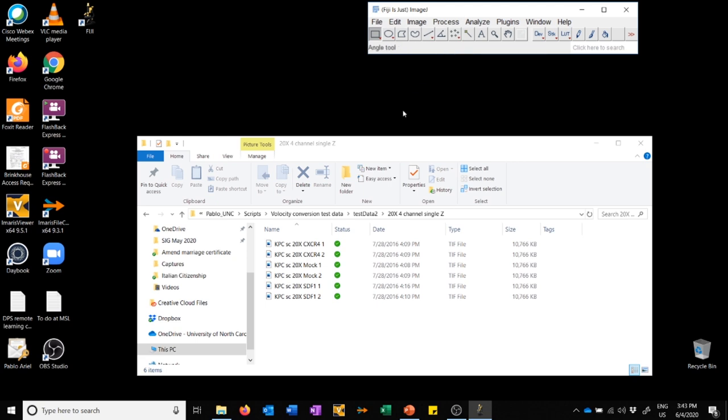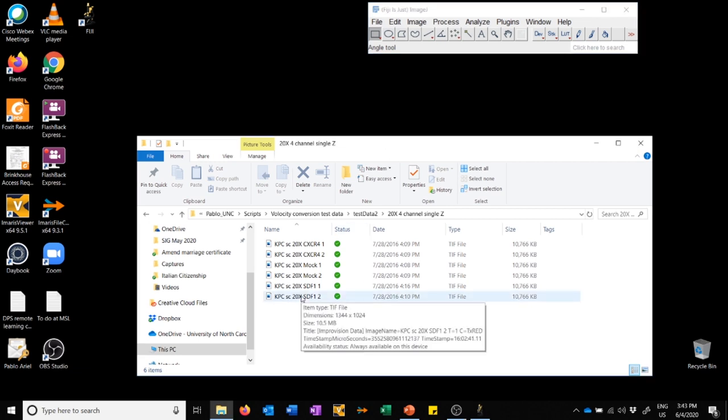So if we go to this dataset and double click on any of these OME TIFF files, what happens is that when we look at it in the Windows Viewer, it's completely dark. The reasons for this I'm not going to go into right now, but it has to do with the bit depth of the images. Just trust me that when you do this, particularly on the BX61, you're going to have this problem. This does not mean that your data is not here. It just means it's being displayed incorrectly. The steps we're going to take will help you be able to display the data correctly in a way that's easy to share with colleagues.